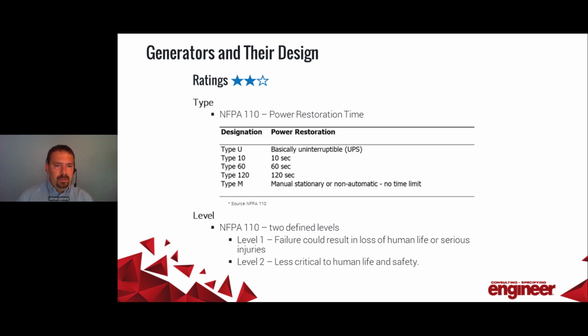And then the type, also defined by NFPA 110, is the power restoration time. So this is the maximum amount of time between when the utility fails and when your standby emergency generator set, your system, backs up the load. So you'll find type 10, 10-second requirement, NEC 700 emergency loads require 10-second transition maximum time, among other types of systems. But this is generally to get you familiar with the types that are listed in 110.